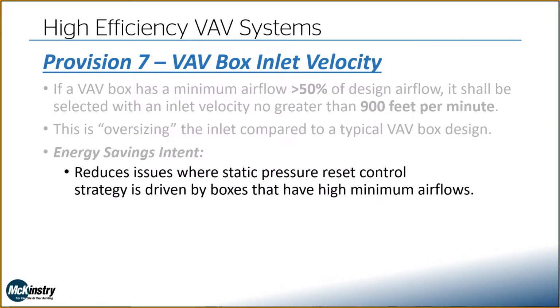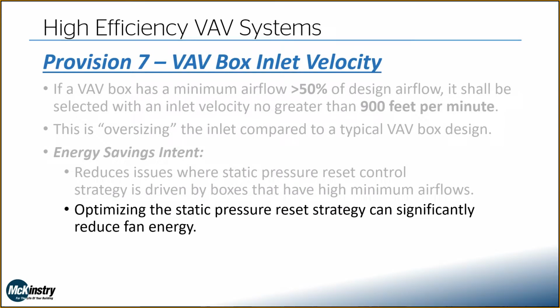The intent here is we can reduce issues where our static pressure reset control strategy is driven by boxes that have high minimum airflow. You can get in a condition where you have a handful of boxes that have these high minimum primary air set points, and they end up driving the entire system. But if we can oversize those boxes a bit, then that'll allow us to reset down to a lower pressure set point. And ultimately, anything we can do to optimize that reset strategy can save a lot of fan energy.